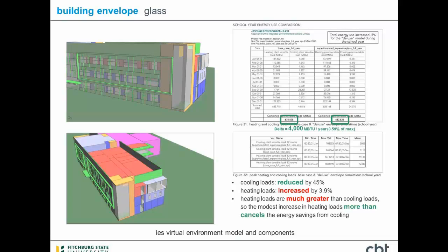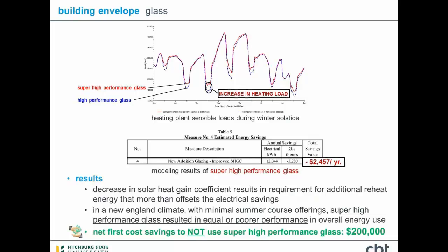When we looked at it in terms of the aggregate amount of energy, it was 4,000 megaBTUs, which on the face of it sounded very small, considering it's only about 0.5% of the building's energy consumption. That said, again, working with our consultant, we were able to show that that amount of energy, given our energy costs here, represented about a $2,500 a year additional cost to the project, and that would have been on top of the fact that we spent $200,000 to, in theory, upgrade the glass. So needless to say, we didn't pursue an additional upgrade in the glass.